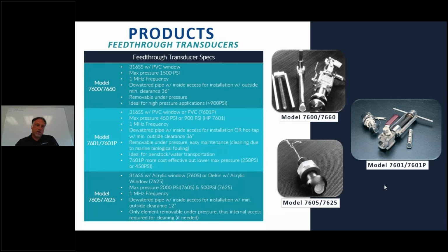Our 7601 and 7601P transducer feed-through assemblies are probably our most popular in the hydroelectric industry. Again, they can be removed under pressure. They are good to about 450 psi, and we have a high pressure version of the 7601P feed through that's good to 900 psi. And again, fully removable under pressure. The ball valve gets moved to a tool as opposed to on the feed through assembly.